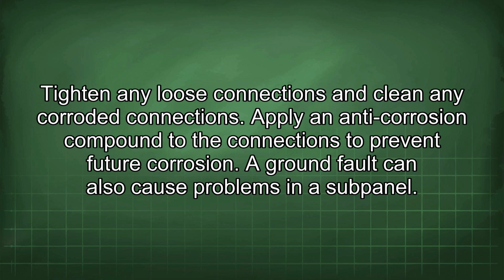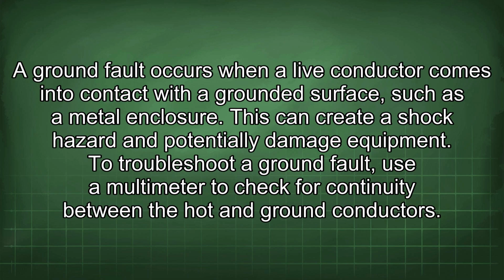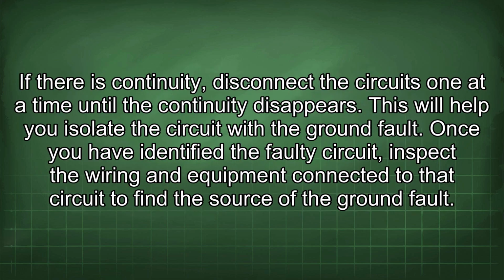A ground fault can also cause problems in a subpanel. A ground fault occurs when a live conductor comes into contact with a grounded surface, such as a metal enclosure. This can create a shock hazard and potentially damage equipment. To troubleshoot a ground fault, use a multimeter to check for continuity between the hot and ground conductors. If there is continuity, disconnect the circuits one at a time until the continuity disappears. This will help you isolate the circuit with the ground fault.